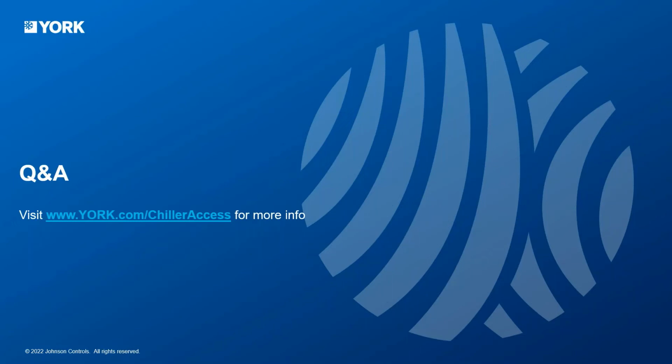Okay, I think this is an important one. If there's maintenance that's required, is the chiller going to lock down and only be able to be accessed with someone at enhanced or JCI service level access? No. If maintenance is required, today, chillers keep operating. They should not get shut down. You're not going to be locked out because you need to do maintenance. I'll be honest, the control panel's not smart enough to do that. We're not stopping the chiller from operating just because maintenance needs to occur. I think maintenance is good practice, but we definitely want to keep the chillers up and running and make sure that your Chiller Access Manager is not controlling whether or not the chiller is on or off.